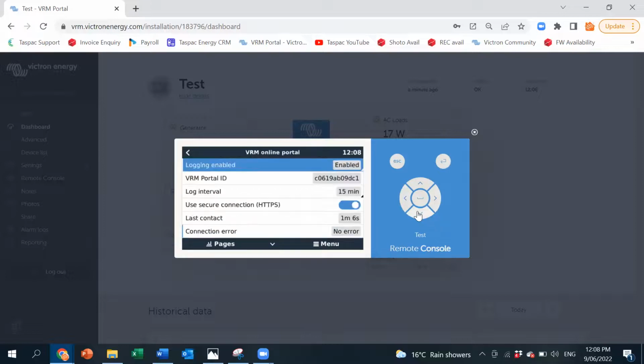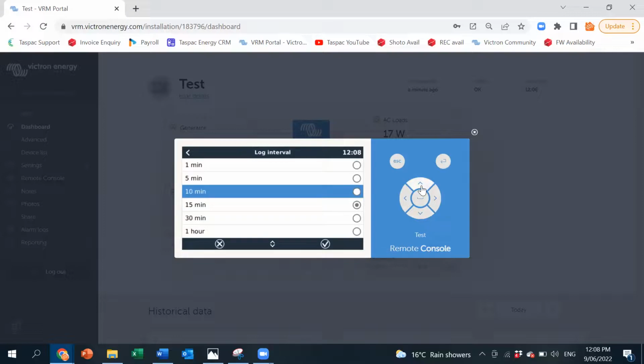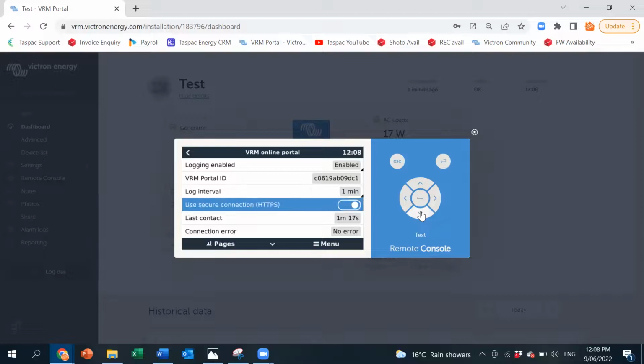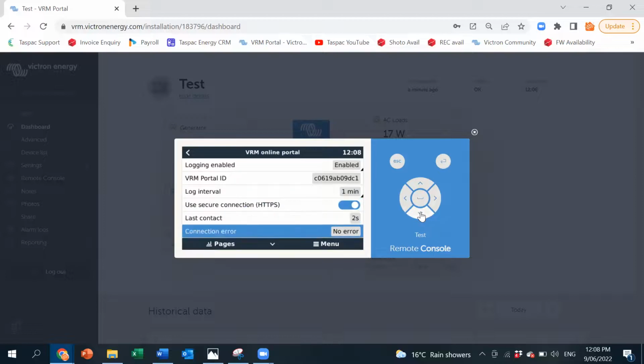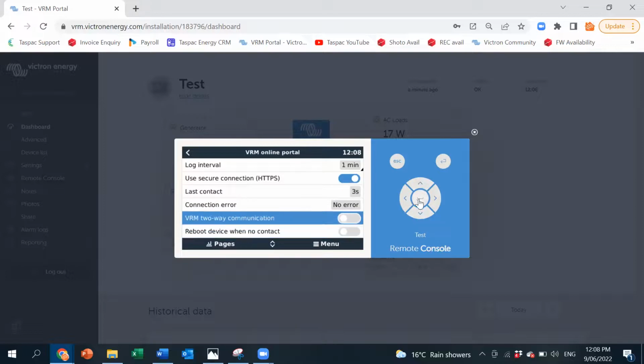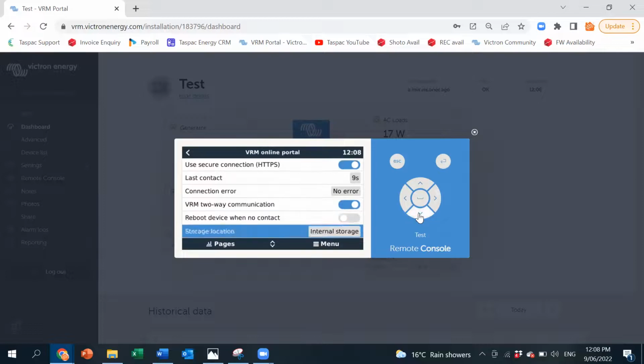VRM online portal, what's going on there? Now, I normally will set this up at 1 minute intervals for the data so that when we're doing fault finding, we can get a really good fine granularity on the data, which really helps. Now, also set up two-way communication, which is important for things like firmware updates remotely, etc.